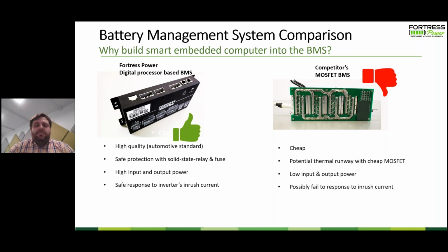That digital processor is related to high amperage, high quality components. The processor will independently control the charging and discharging and pre-charging relays on the batteries, so that they manage charging and discharging independently through independent relays. That gets you more life on your relays, for example, so that the battery lasts the full 10-year duration and beyond.